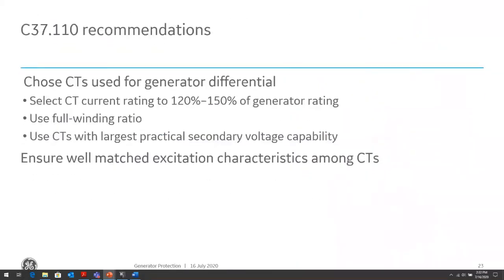So the C37.110 recommendations for CT sizing are about 120 to 150% of the generator rating. Use the full winding ratio, meaning if you have a multi-tap CT, try to use the full winding, because if you use one of the tap windings, that will reduce the rating of the CT by the amount of that tap. For example, if you have a 2000:5 CT and you use the 1000:5 tap, you're effectively reducing the rating of the CT by as much as half of what it's capable of.